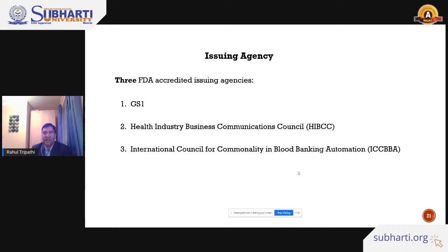So mostly GS1 gives class 1 UDI numbers, whereas in class 3, there is the International Council for Commonality in Blood Banking Automation. So you can see by the name, blood banking or related to blood transfusion medical devices, you need to go to the International Council for Commonality in Blood Banking Automation. You can go and ask this agency, can you give me a UDI number for my medical device? Whereas if you are using a general medical device, you can go to GS1 and get a UDI number assigned for your medical device.